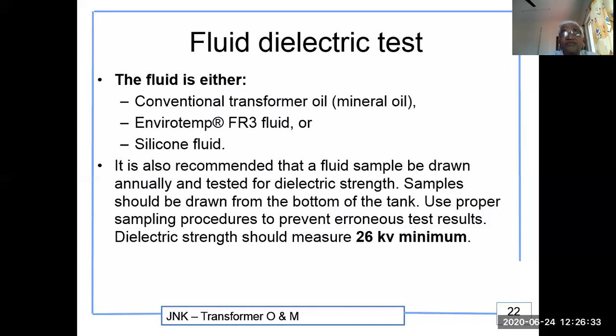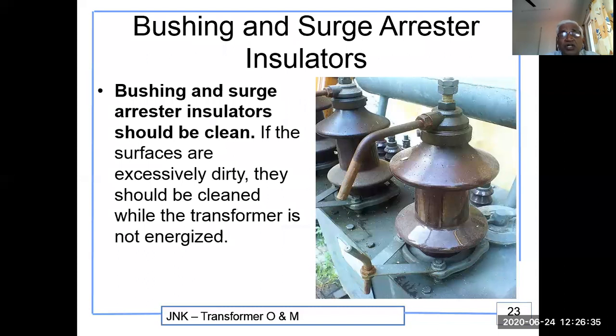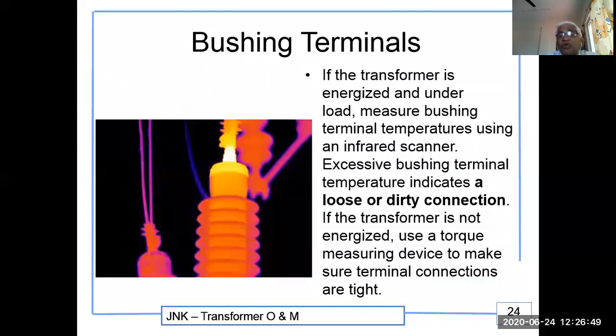Bushing and surge arrestor insulators. Bushing and surge arrestor insulators should be clean. If the surfaces are excessively dirty, they should be cleaned while the transformer is not energized. Bushing terminals. If the transformer is energized under load, measure bushing terminal temperature using an infrared scanner. Excessive bushing terminal temperature indicates a loose or dirty connection. If the transformer is not energized, use a torque measuring device to make sure terminal connections are tight.